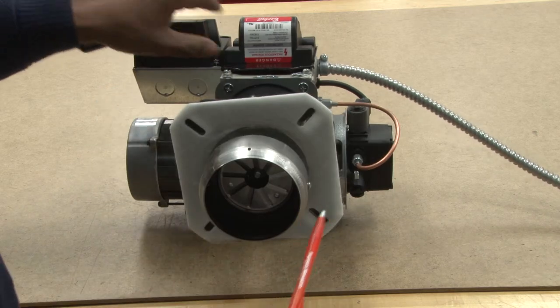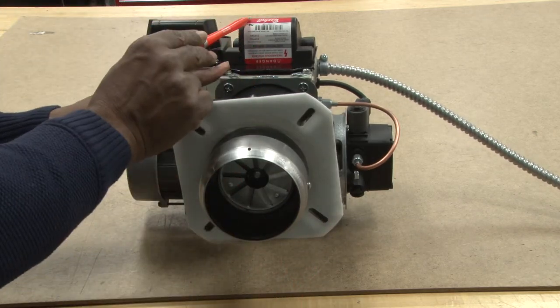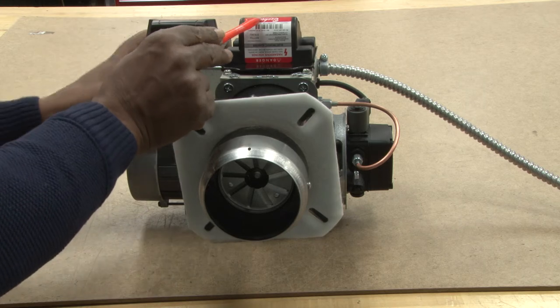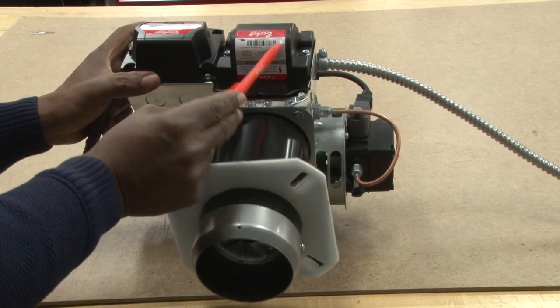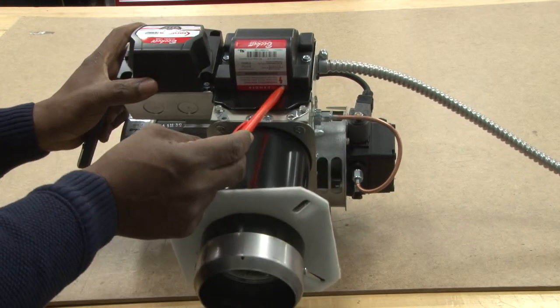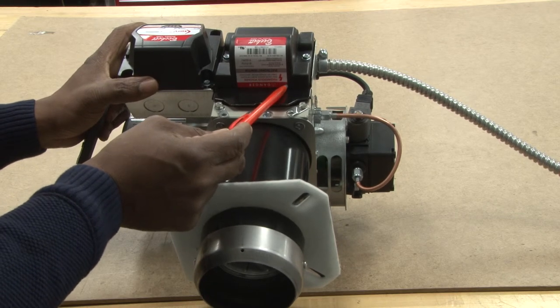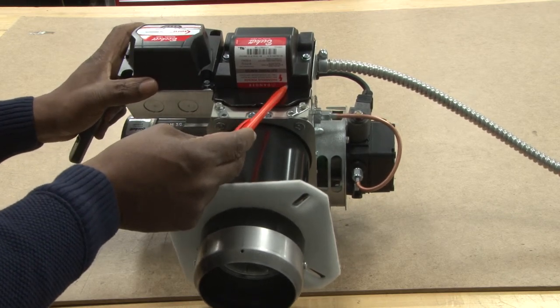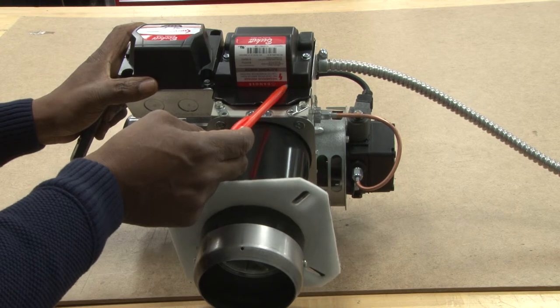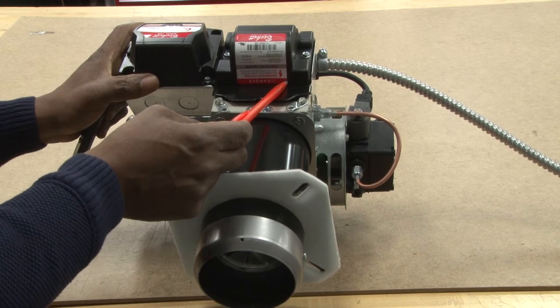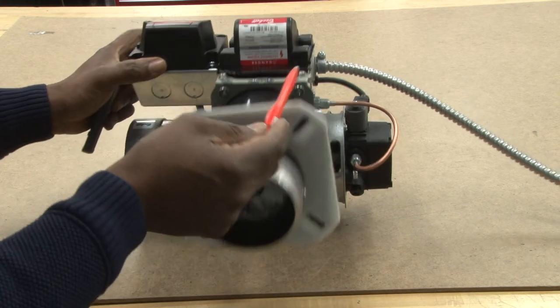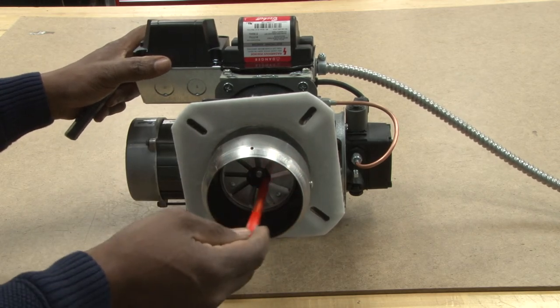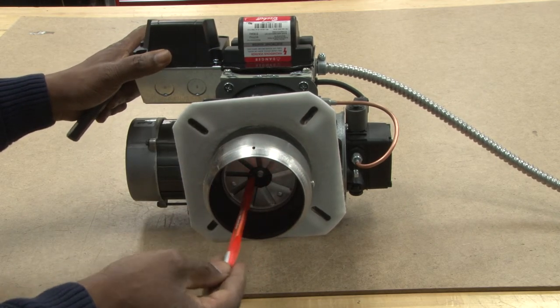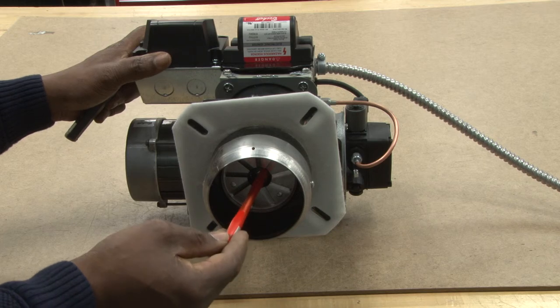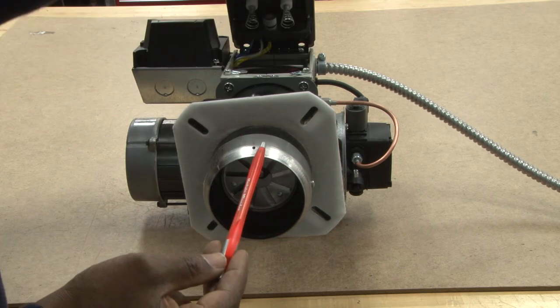A couple other components: the very top of it is the ignition transformer. It's a high voltage step-up transformer which will produce between 8 to 10,000 volts, very high voltage but low current, to make a spark for the ignition of the flame for the oil mist from the nozzle. Open it up so you can see it.